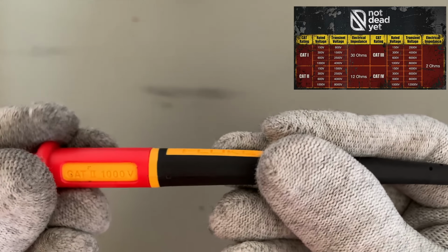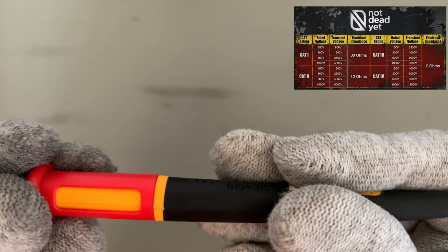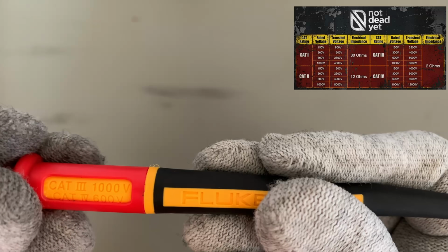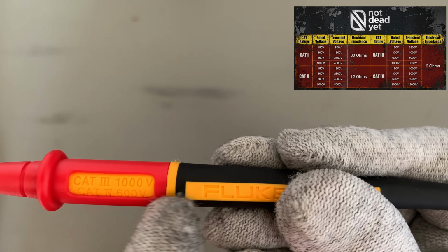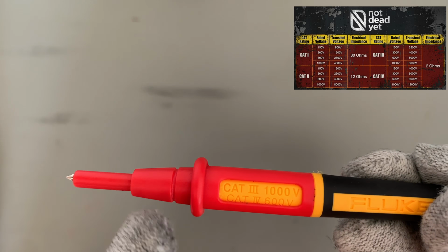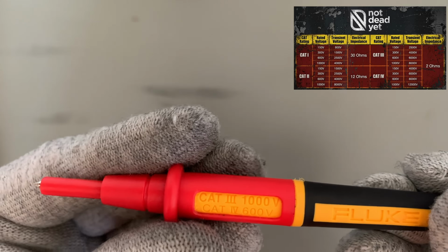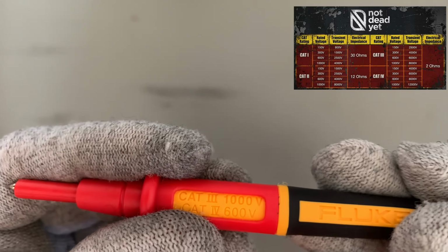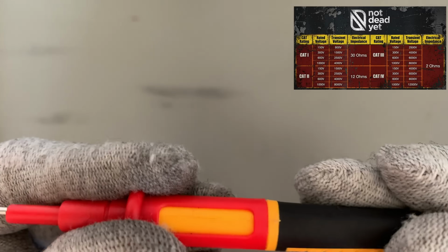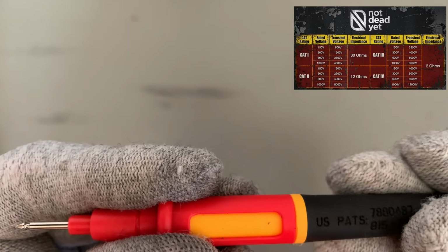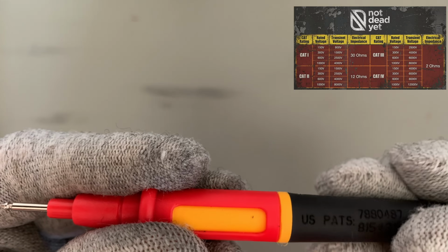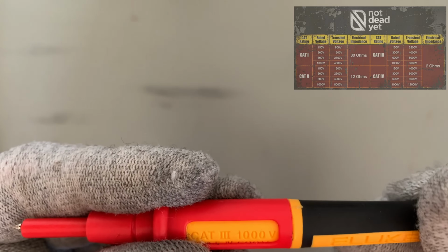Why this matters? The category is not about the steady voltage, it is about the transient energy the leads and the meter can survive when something upstream goes wrong. A higher category at the lower voltage is a tougher rating than it looks. The rule is simple. Your test leads must carry at least the same CAT rating as the environment you are measuring in. Undersized leads are how you get an arc across your hands instead of a reading on your screen.